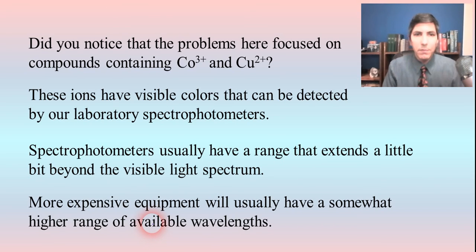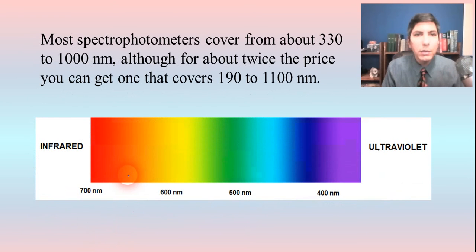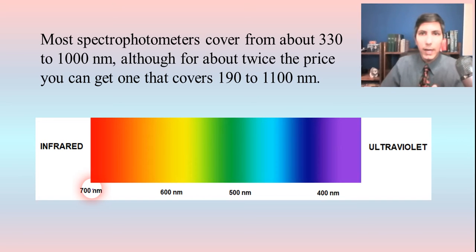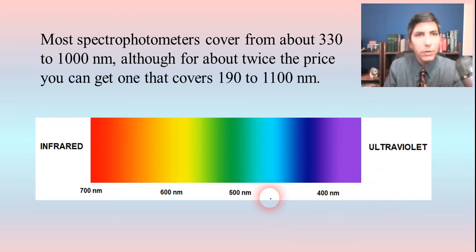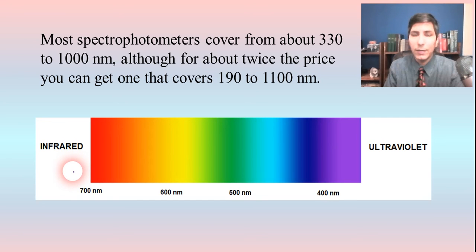Most spectrophotometers have a range that goes a little bit beyond the visible spectrum — roughly 400 to 700 nanometers. Most lab instruments go from about 330 nanometers up to about 1,000, which actually runs into the infrared. If you go up in price, you can increase your range, maybe getting all the way down to about 190 nanometers and up a little bit higher than 1,000.